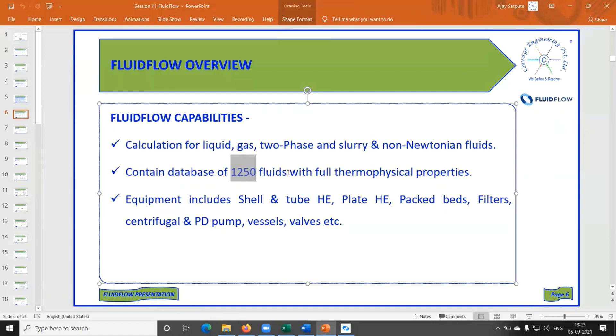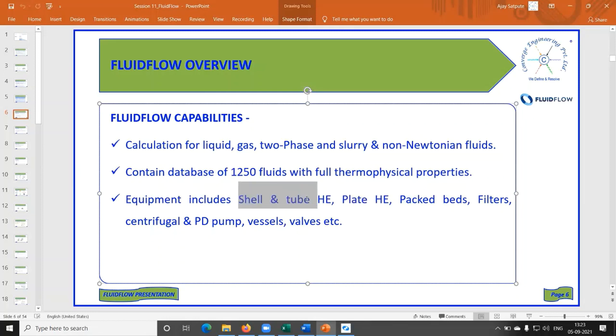Fluidflow also includes a lot of equipment models — shell and tube heat exchangers, plate heat exchangers, back-pressure valves. If your fluid goes through the tube side of a shell-and-tube heat exchanger, it calculates the pressure drop based on tube ID, tube length, and number of tube passes. In other software, you provide a reference value — say, at 100 m³/hr the delta P is 0.5 bar — and it extrapolates, whereas Fluidflow gives you an accurate number.